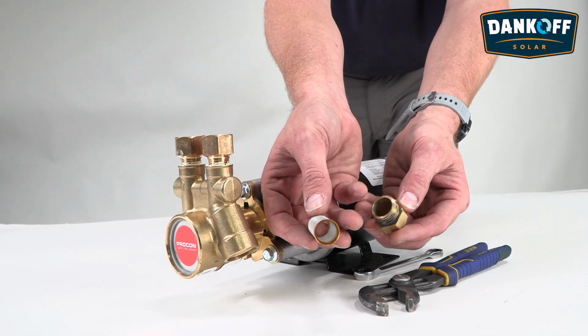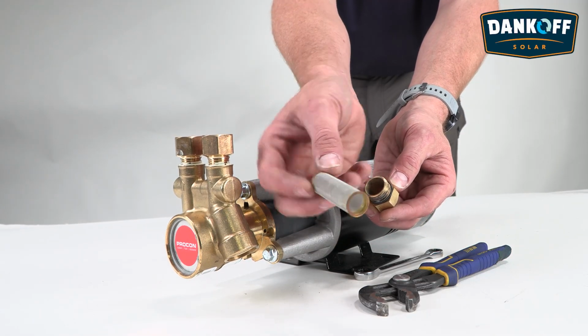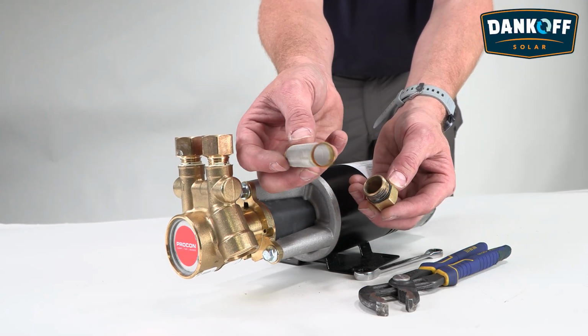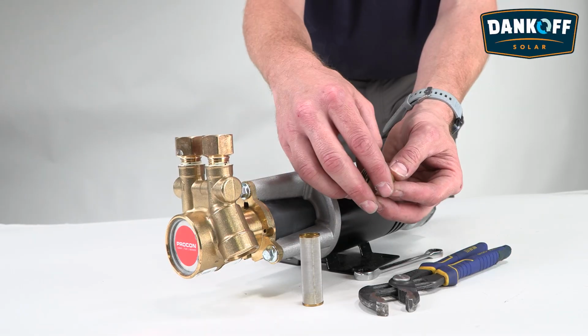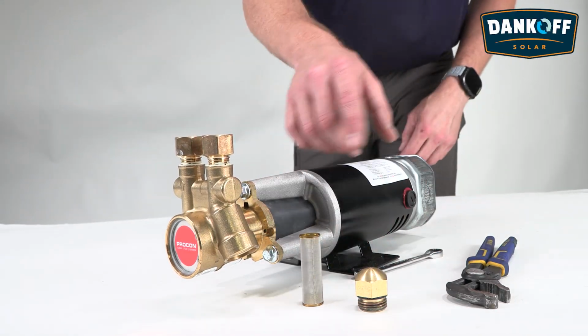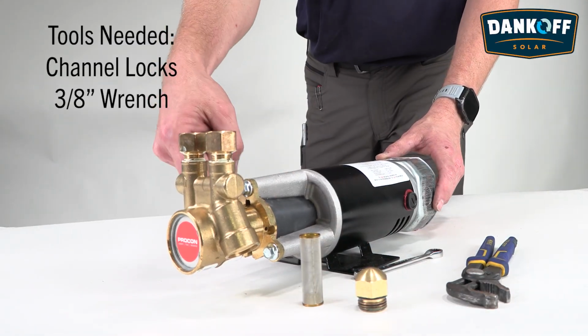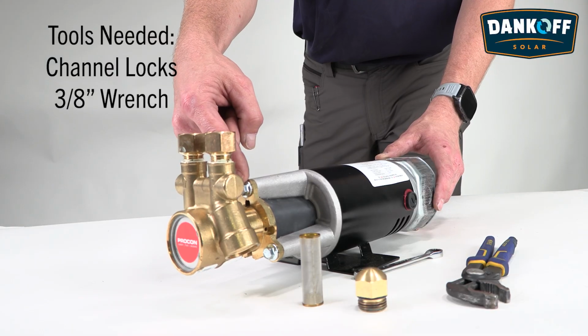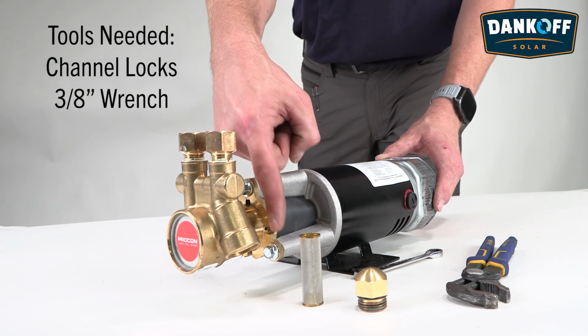You'll want to start the process with a pair of channel locks, then remove completely with your hands. Once removed, you'll find a screen. Clean if necessary. Ensure all water has drained. If you're located in less harsh environments, for example down south, we can leave it here. If you're located in the northern hemisphere, we'd recommend removing these 3 bolts located at the front of the motor holding the pump end on.